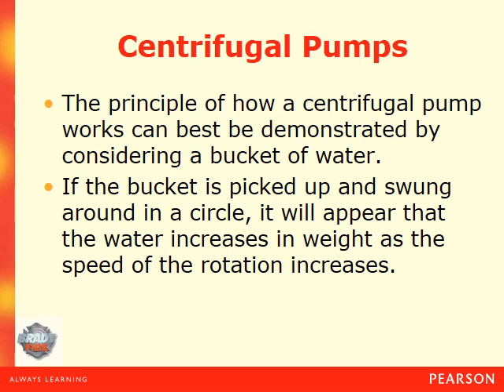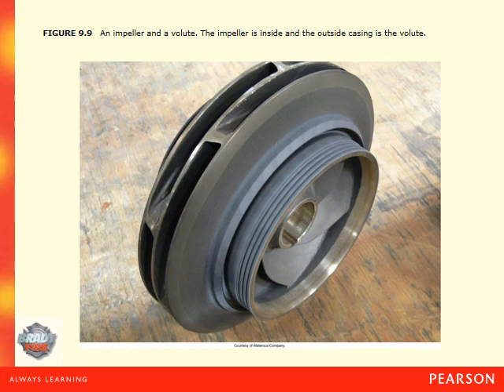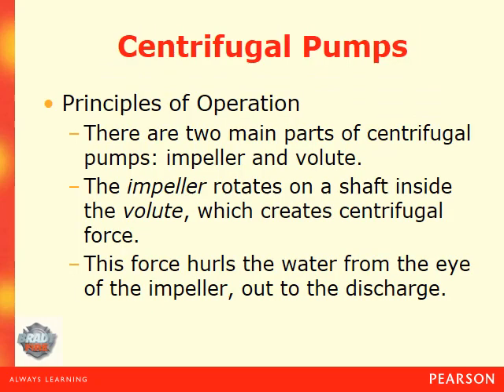The principles of how a centrifugal pump works can best be demonstrated by considering a bucket of water. If the bucket is picked up and swung around in a circle, it will appear that the water increases in weight as the speed of rotation increases. By poking a hole in the bottom of the bucket, the faster it is swung, the greater the discharge and the farther the water will be discharged — this force is referred to as centrifugal force. There are two main parts of a centrifugal pump: the impeller and the volute. The impeller rotates on a shaft inside the volute, creating centrifugal force that hurls water from the eye of the impeller out to the discharge.